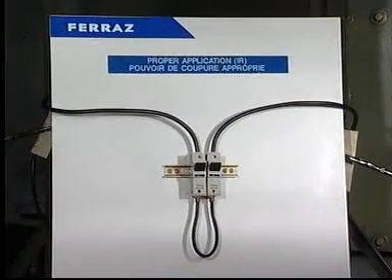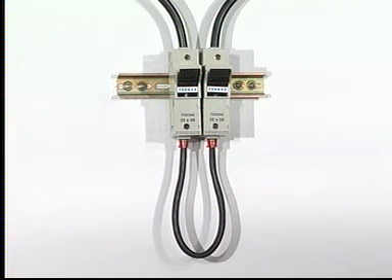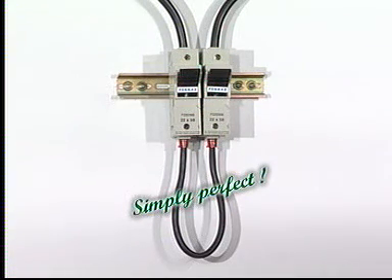The fourth and last test shows fuses with adequate interrupting rating of 200,000 amperes exposed to the same 25,000 ampere fault. The fuses open safely. Fuses are sealed devices. Resultantly, there is no outgassing to the surrounding area.